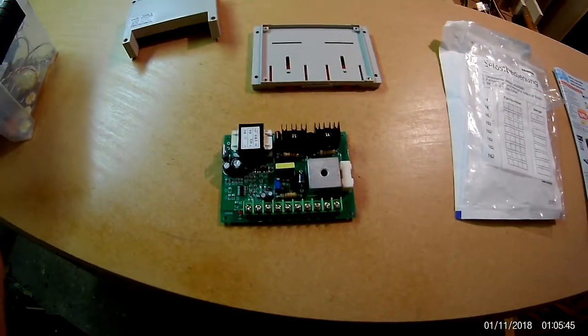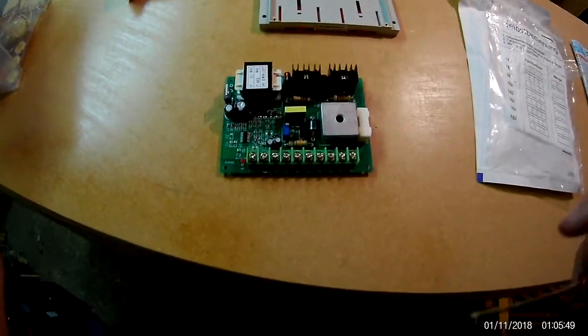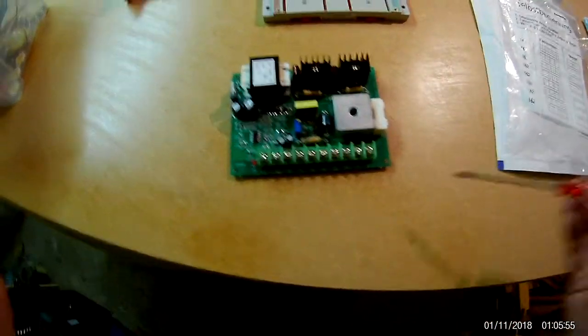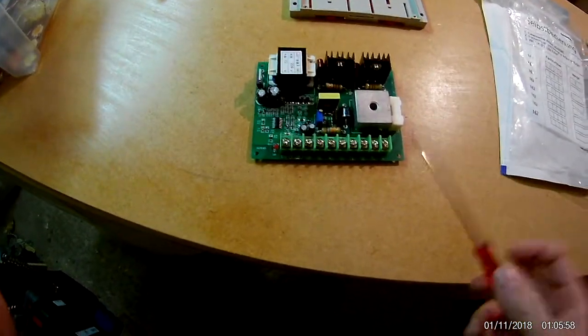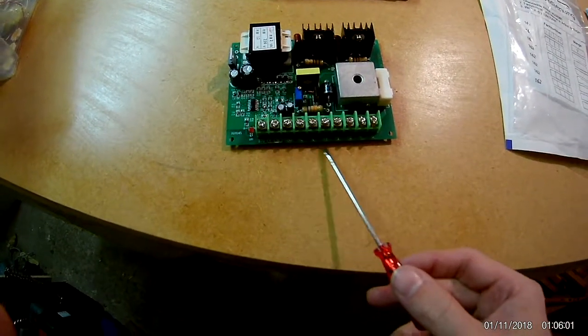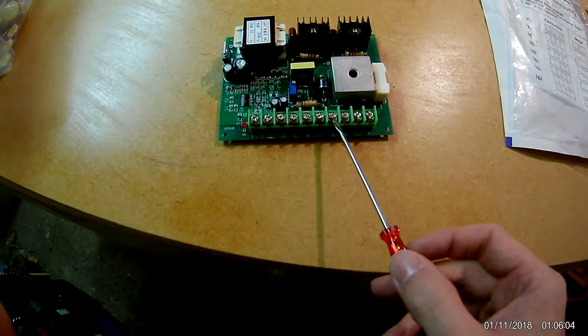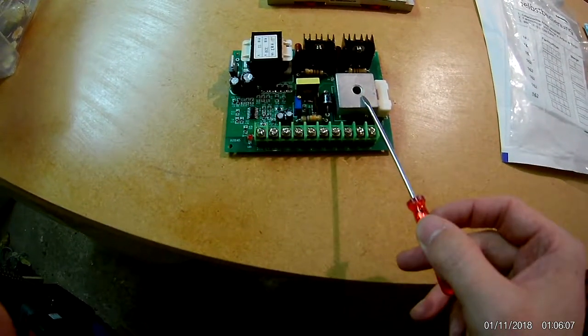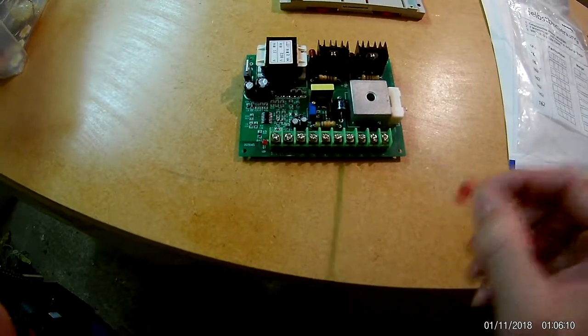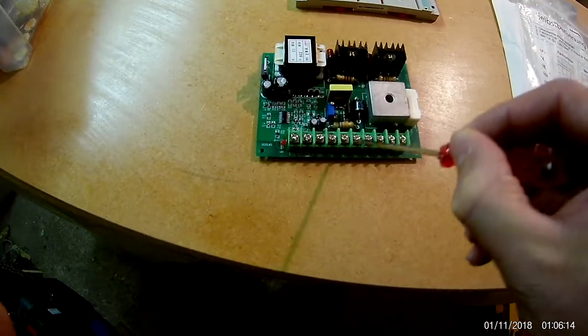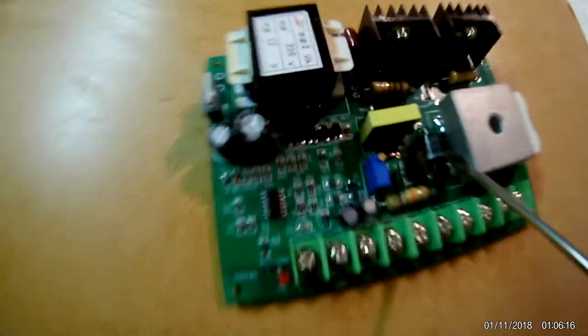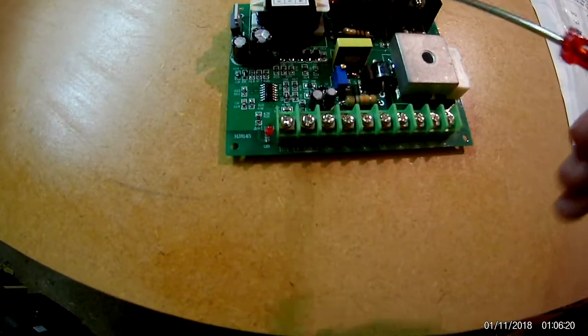That's not entirely correct. The output, the DC max would be the root of two times the input voltage. In our case that's 230 volts AC input, so 340 volts DC output at A minus and A plus. I think A minus is directly connected to F1 which directly goes to line through the rectifier. F2 is directly to the rectifier and A plus goes through the MOSFETs. We have this big super big diode, that's the flyback diode, protects the MOSFETs from flyback from the induction of the coil.